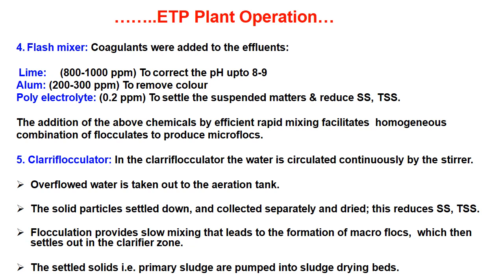Number five is the clariflocculator. In the clariflocculator, water is circulated continuously by the stirrer. The overflowed water is taken out to the aeration tank. Solid particles settle down and are collected separately and dried, reducing SS and TSS. Flocculation provides slow mixing leading to the formation of macro flocs, which settle out in the clarifier zone. The settled solids — primary sludge — are pumped into sludge drying beds.